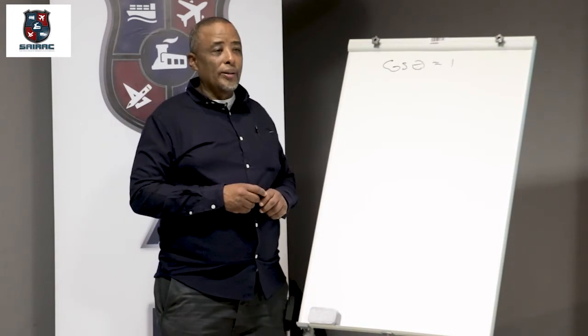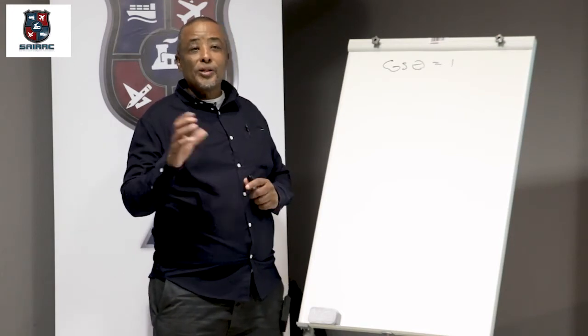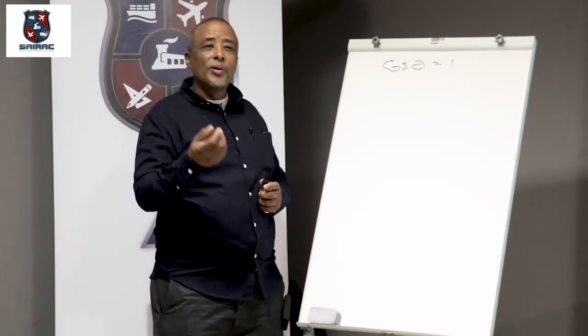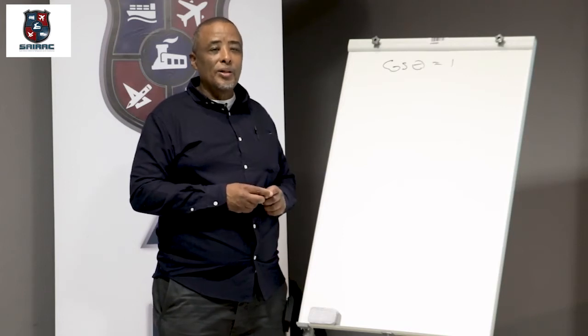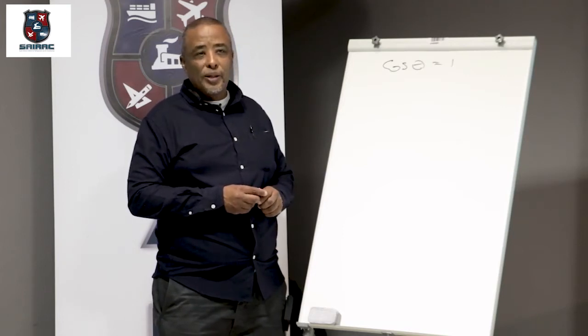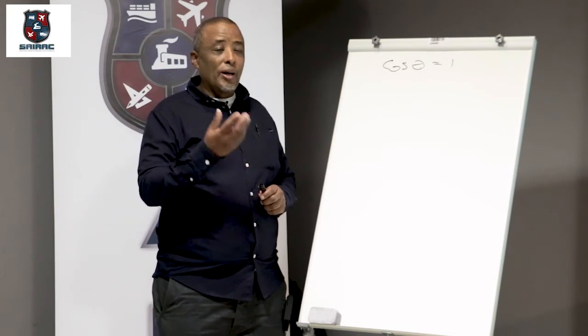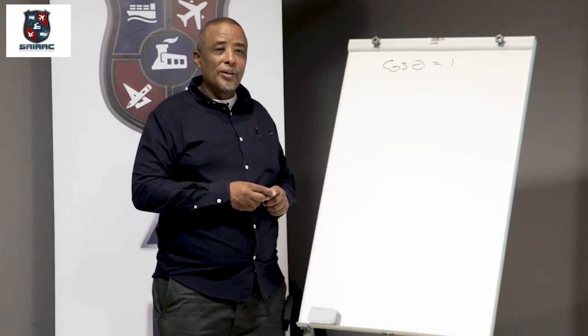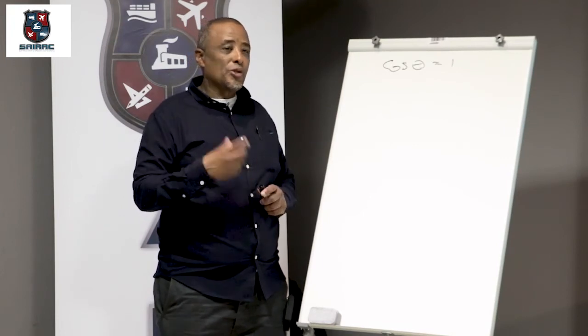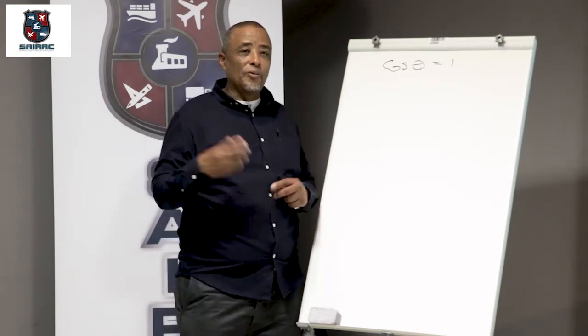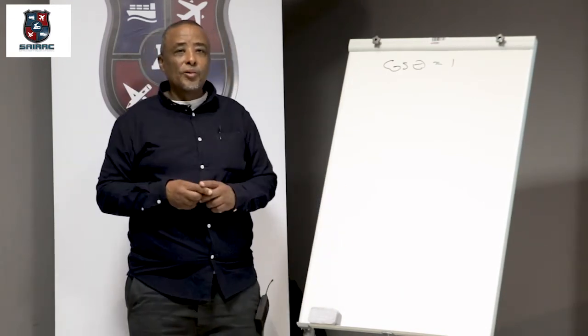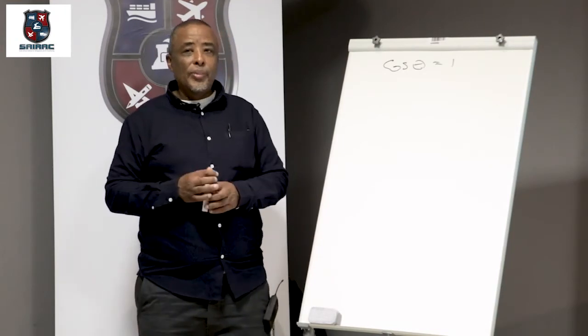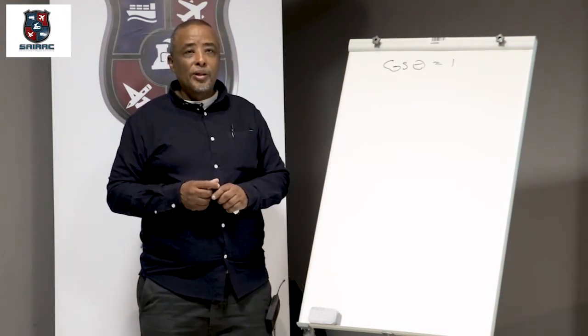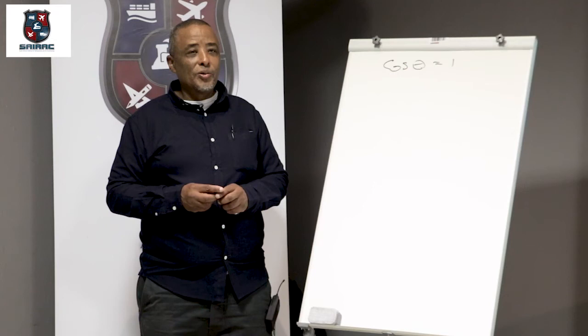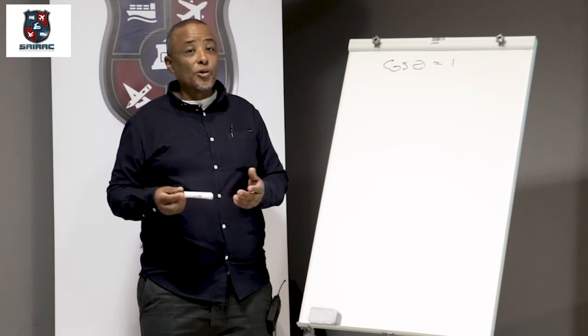This is why municipalities always are on the supply side. If they know about inrush current in a factory, we normally put slow curve breakers and that type of thing. I don't know how you're going to overcome it. Because starters itself, motors itself, if you start delta starters, it starts off high and balances out. That's something that you need to work on. But it does cause a problem.